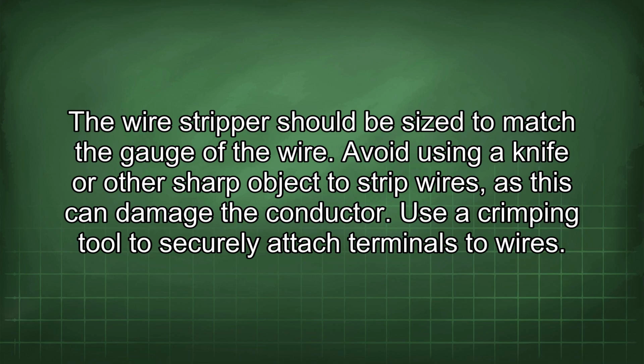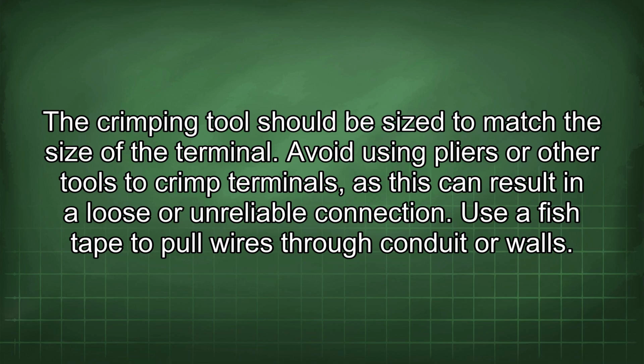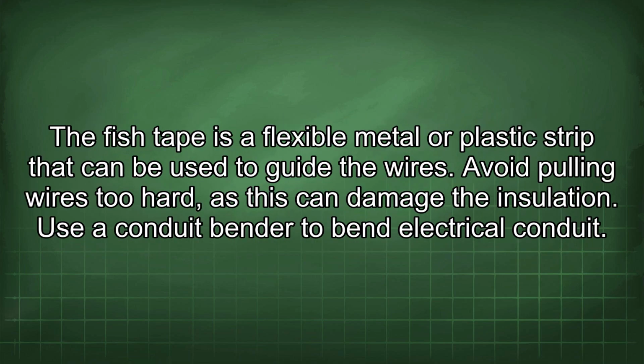Use a crimping tool to securely attach terminals to wires. The crimping tool should be sized to match the size of the terminal. Avoid using pliers or other tools to crimp terminals, as this can result in a loose or unreliable connection. Use a fish tape to pull wires through conduit or walls. The fish tape is a flexible metal or plastic strip that can be used to guide the wires. Avoid pulling wires too hard, as this can damage the insulation.